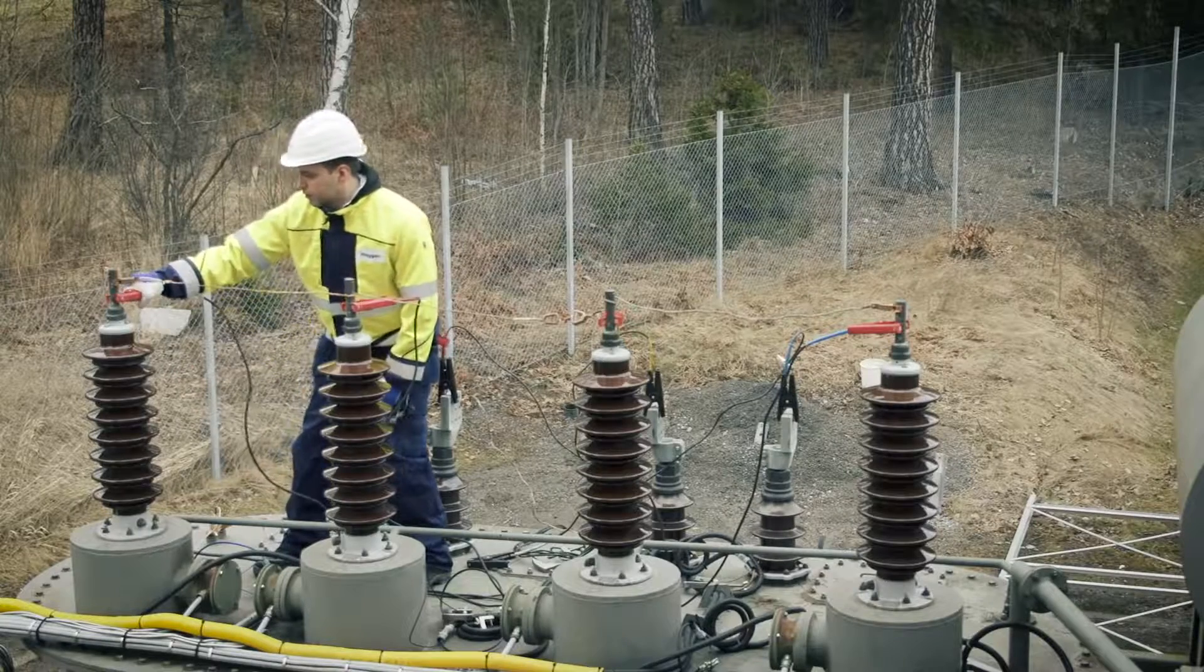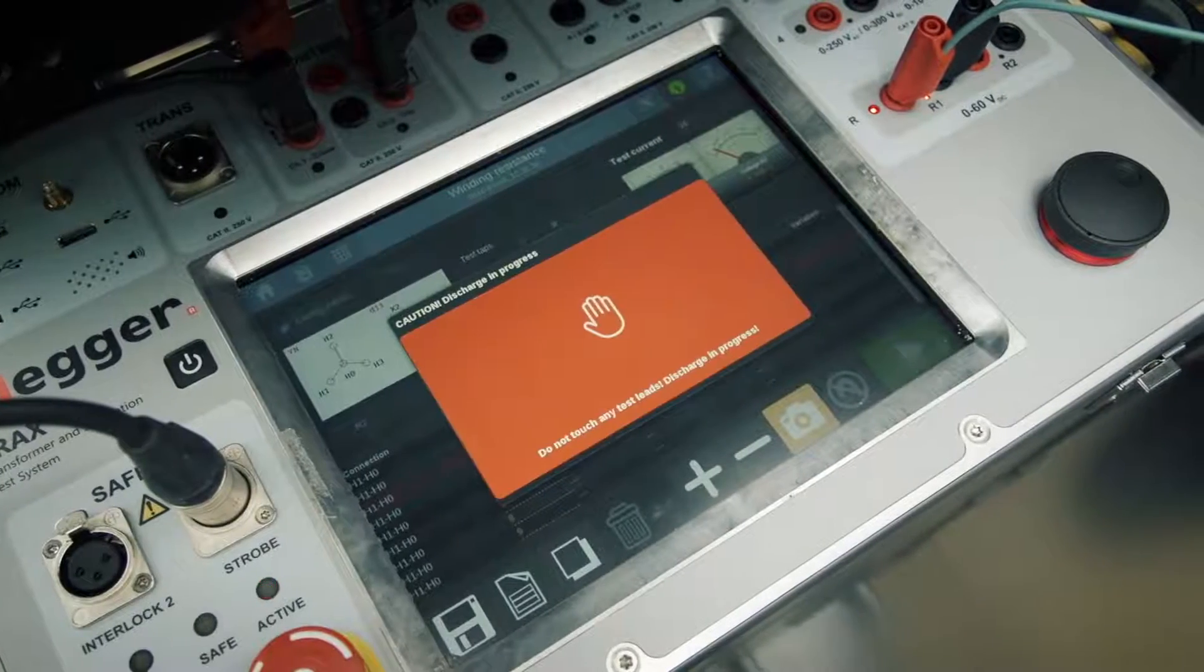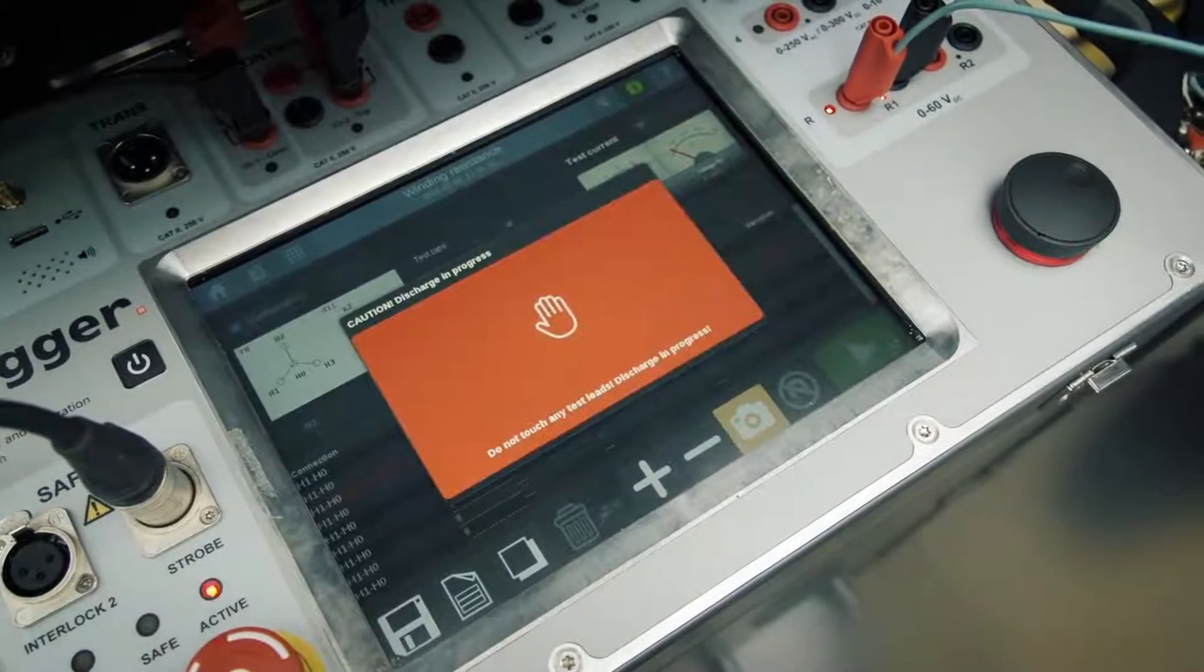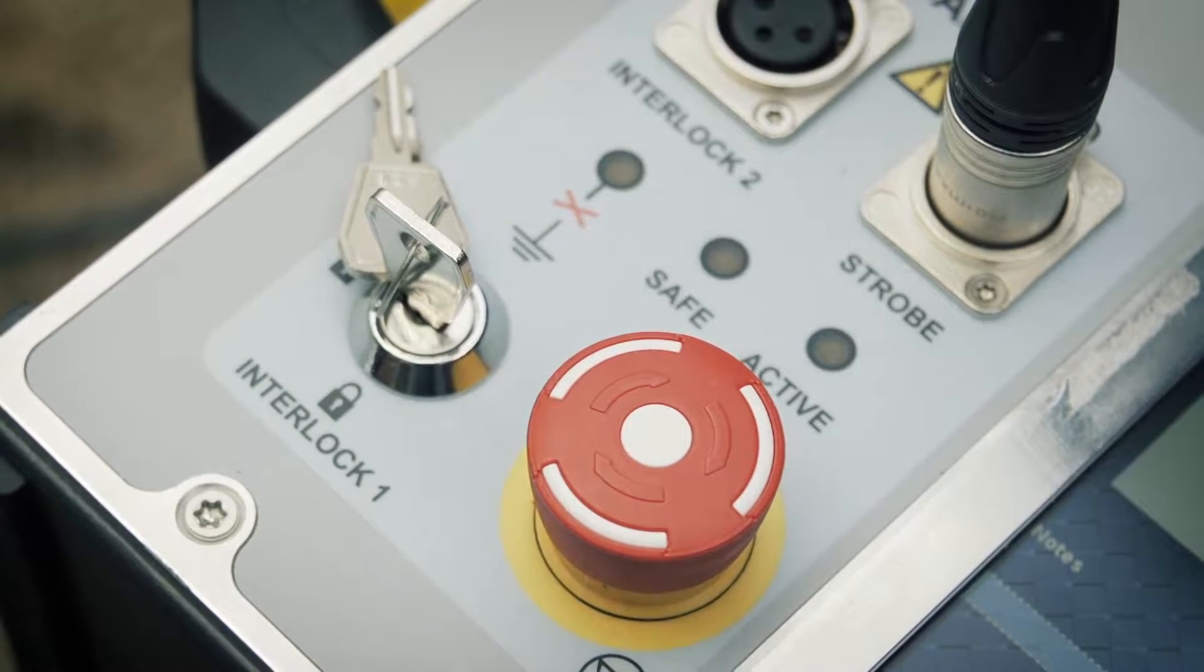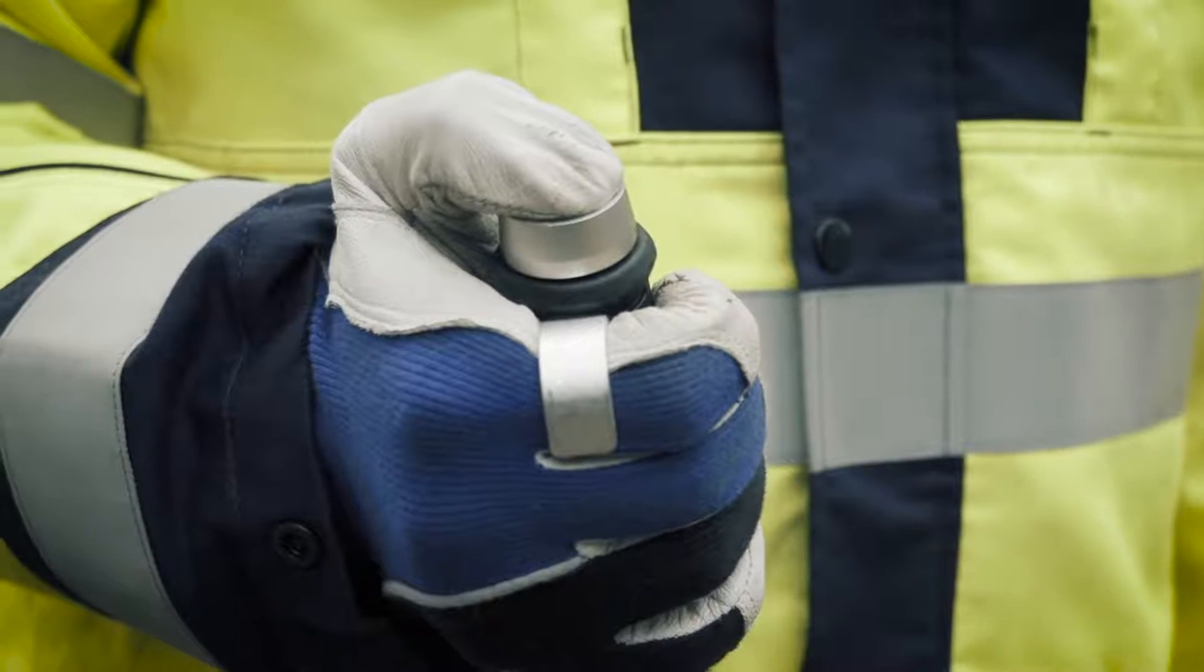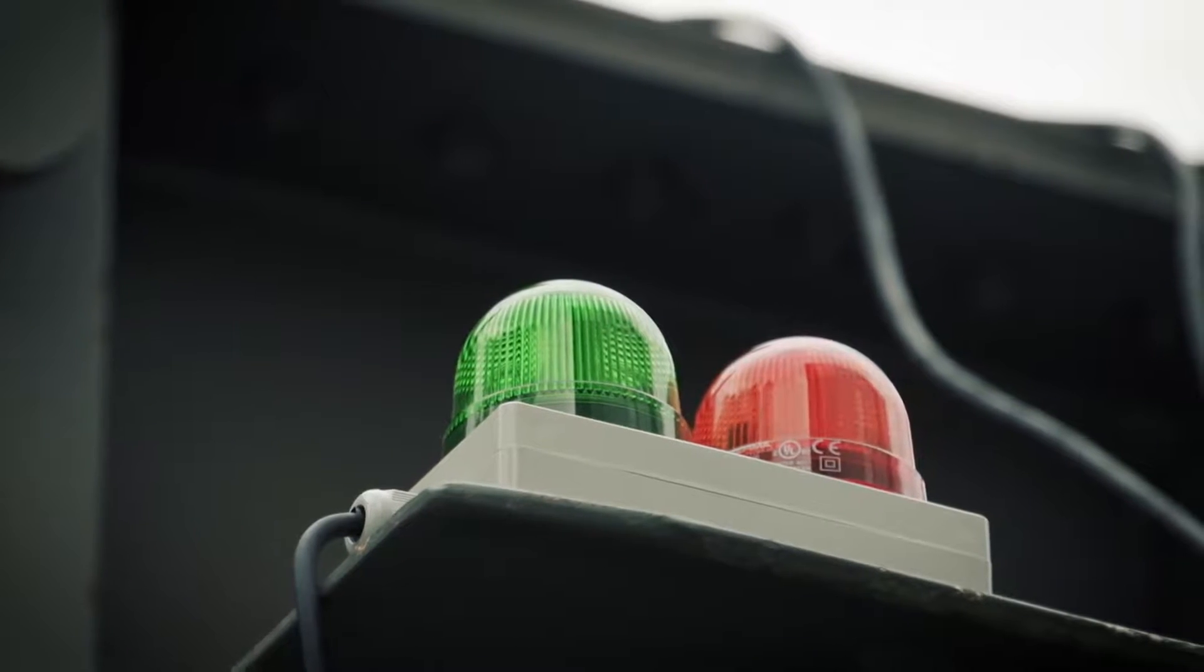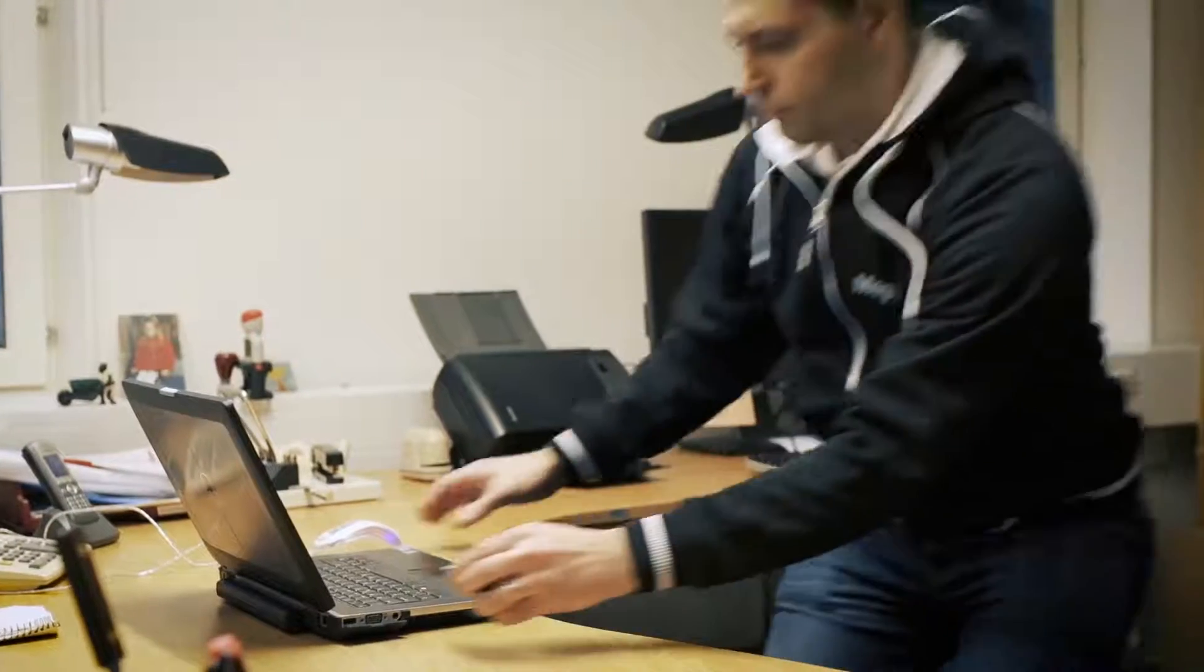TRAX has several inbuilt enhanced safety features including automatic and fast discharge of inductive measurement circuits after a winding resistance test, dual interlock and ground loop detector, optional strobe warning lights, and optional three-phase switch box for one-time connection, thus reducing the number of ladder climbs.